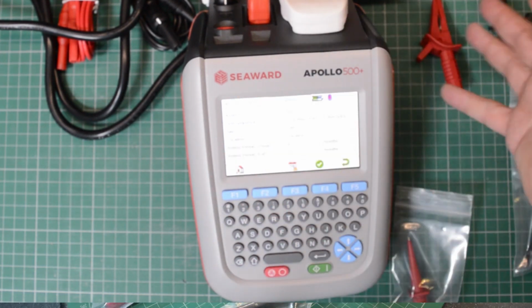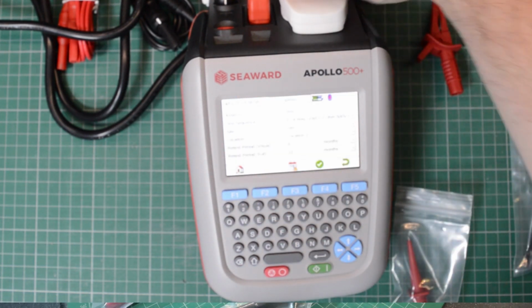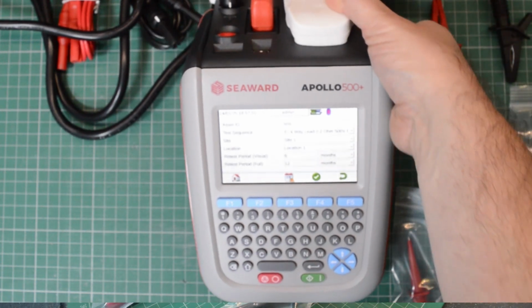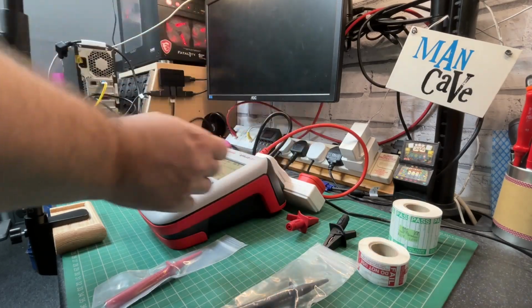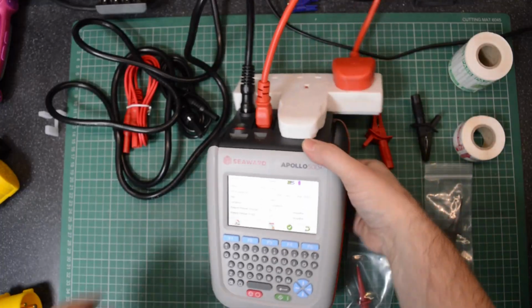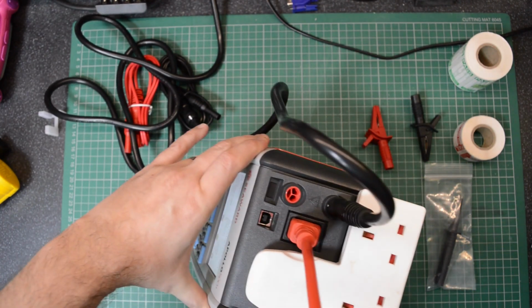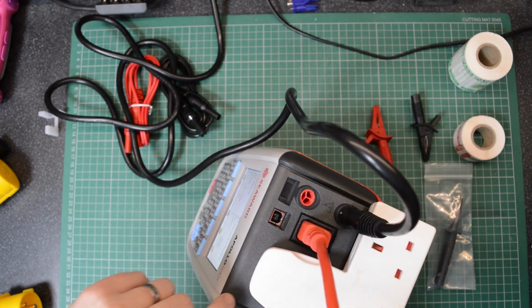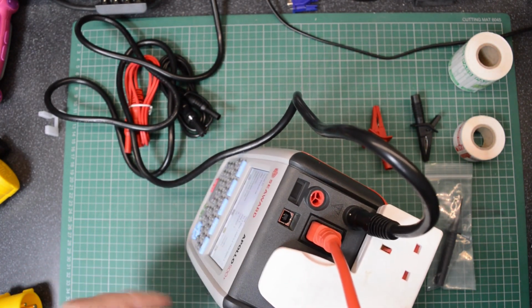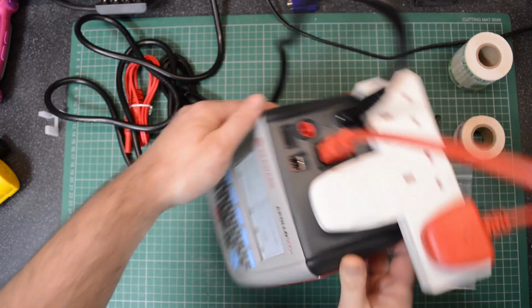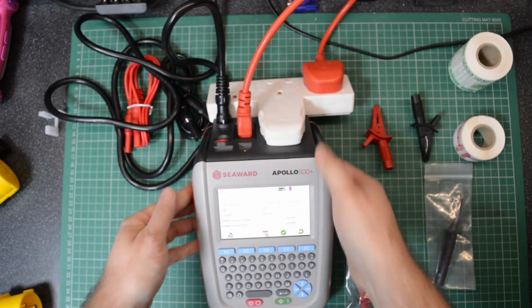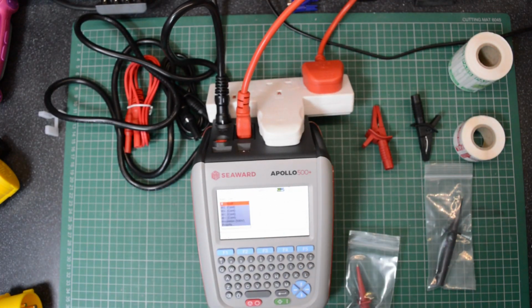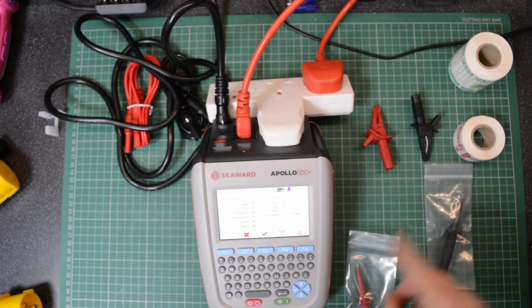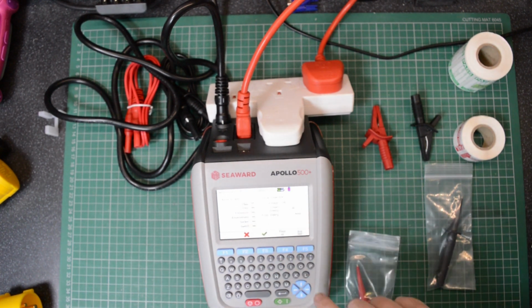I've done a visual inspection. All 3 sockets are okay, there's no damage to anything there. It's got a 13 amp fuse in it, it's fine for this. It should actually say on here, yeah, 13 amp, 250 volts, 3000 watts. So a 13 amp fuse is appropriate. Let's go ahead and do a test. I'm going to pass all for the visual inspections.